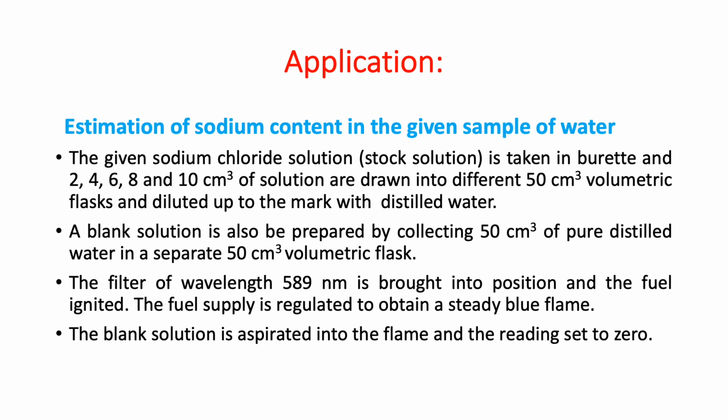Because our distilled water may contain some sodium ions. To nullify that sodium, because we use the same distilled water to fill all the standard solutions as well as our test solution, we aspirate the distilled water into the flame and adjust the instrument to zero emission.